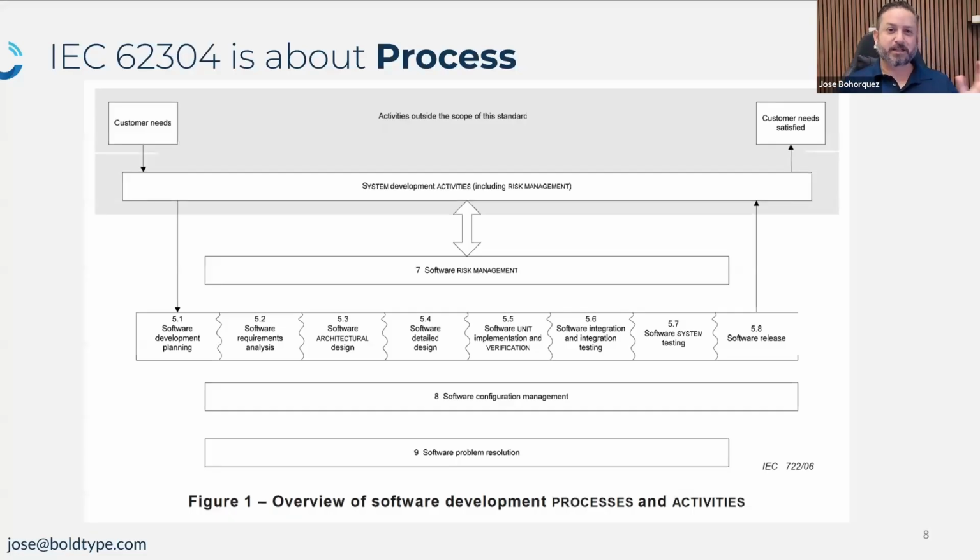So it's not like we're cleared, we're good. There are things that you don't submit to FDA during your 510(k) submission that you still are responsible for doing. And so making sure that you keep your design history file and your quality management system in good shape is critical for long-term success. It can be too short-sighted.